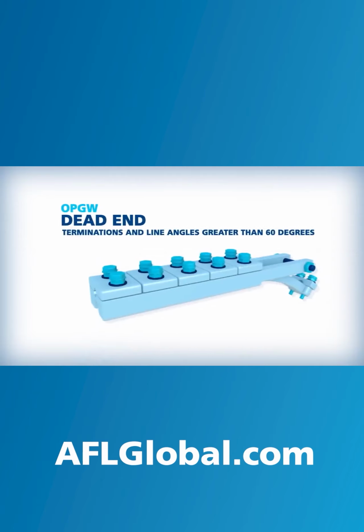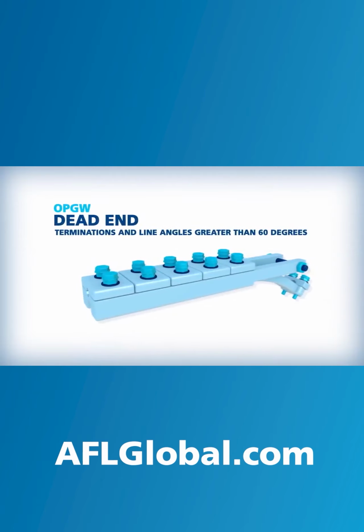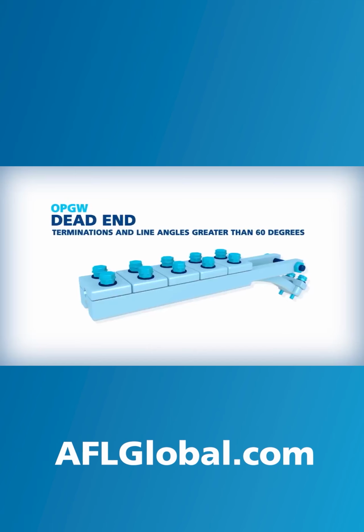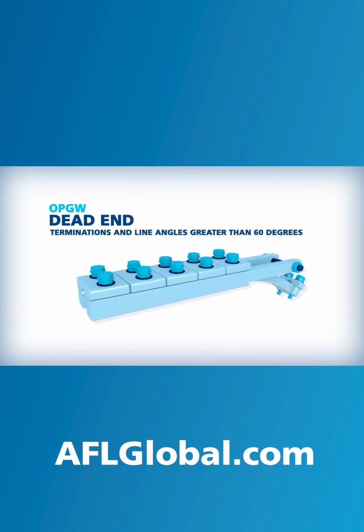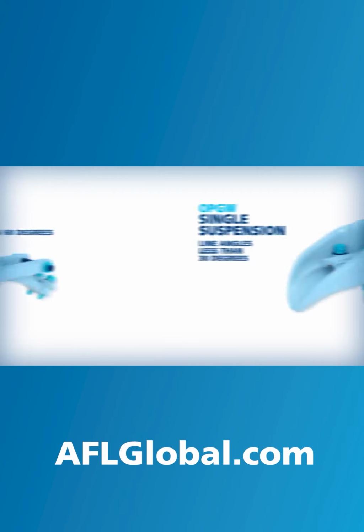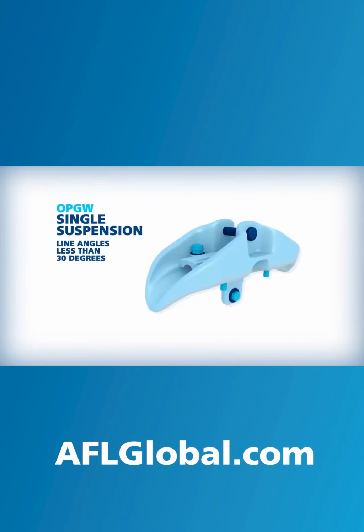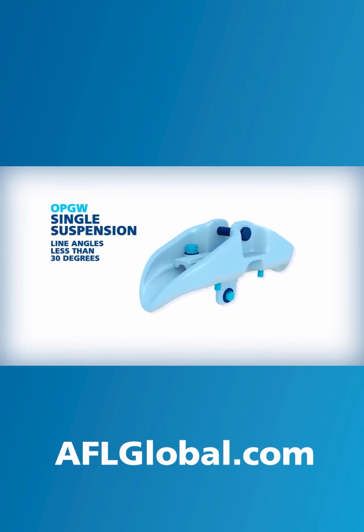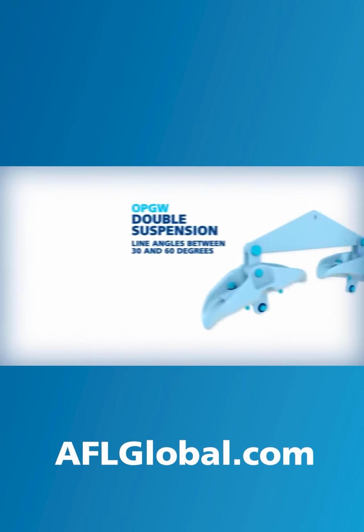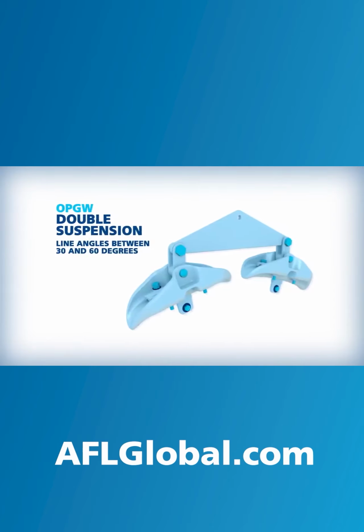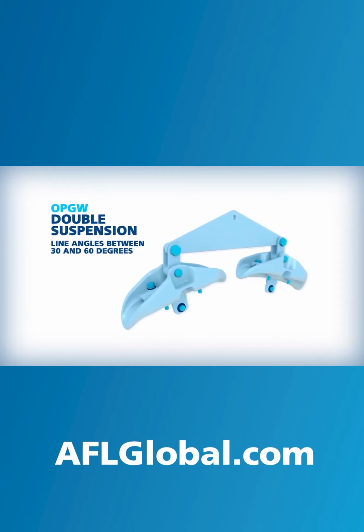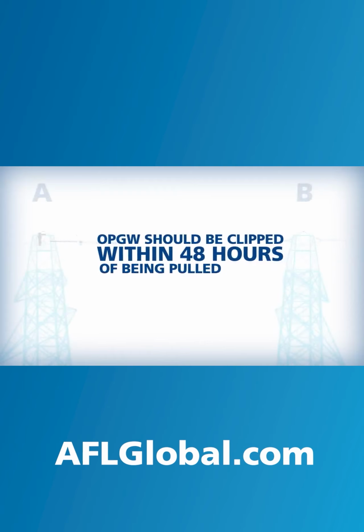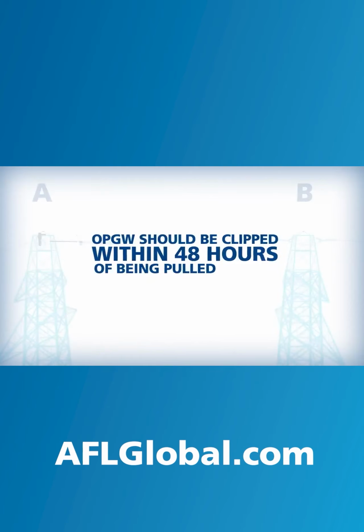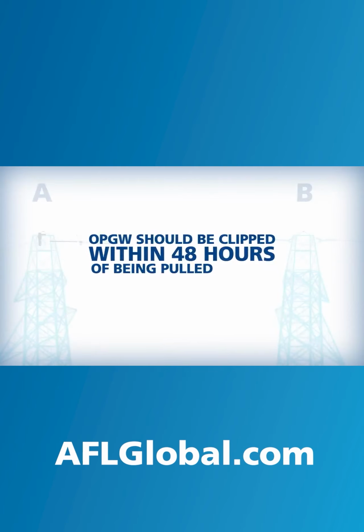Dead ends are used on structures where the OPGW terminates to be spliced, where the line angle is greater than 60 degrees, as well as road, river, and rail crossings. Single suspension clamps are used on structures where the line angle is less than 30 degrees, and double suspensions can be used on structures when the line angle is between 30 and 60 degrees. OPGW should be clipped into dead ends and suspensions within 48 hours of being pulled.